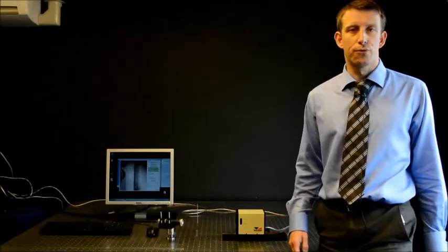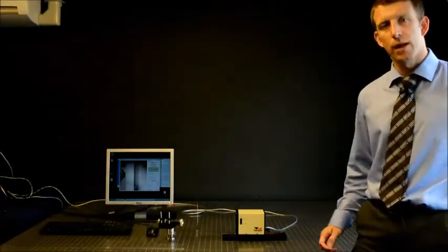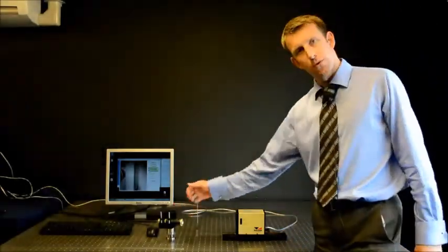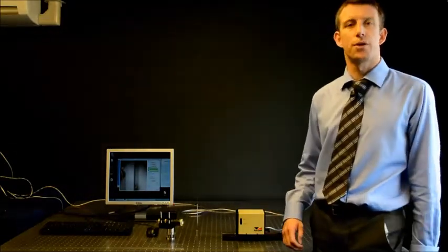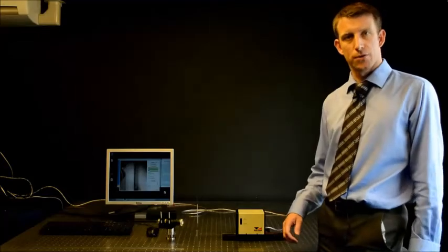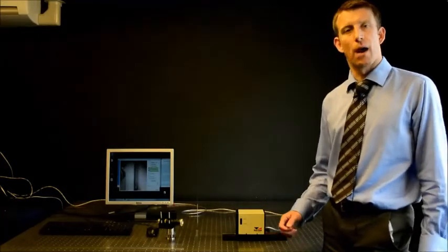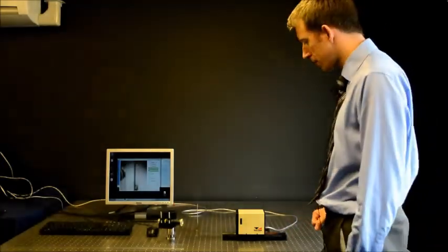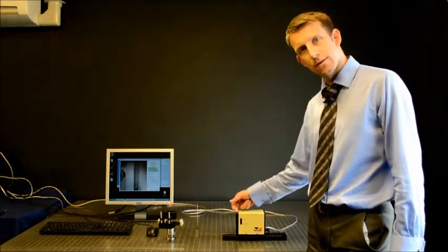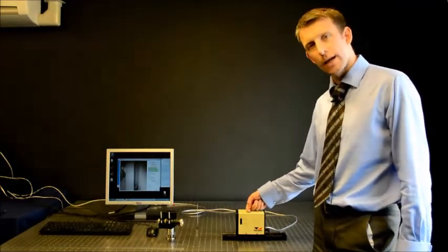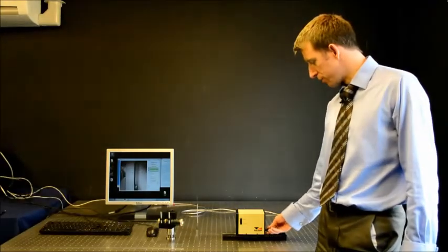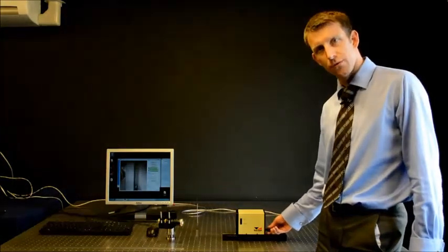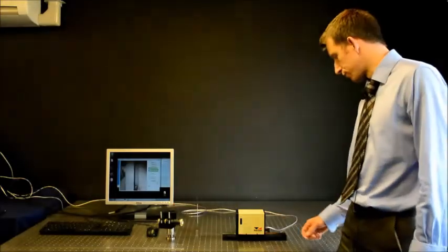The PSL Profiler is based on a two-lens system to image the source under test onto a CMOS camera for the determination of both the angular source subtense and the apparent source location. The first lens is fixed, the second lens is translatable and can be moved using a screw to the rear of the PSL Profiler.